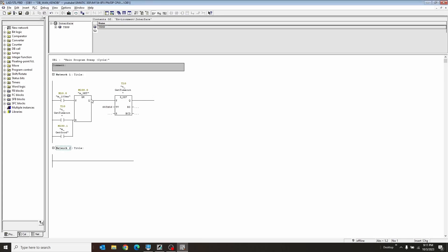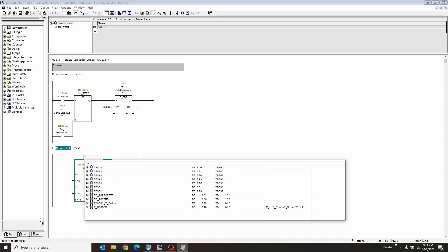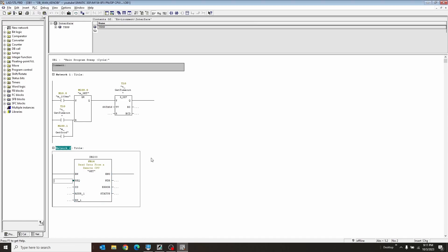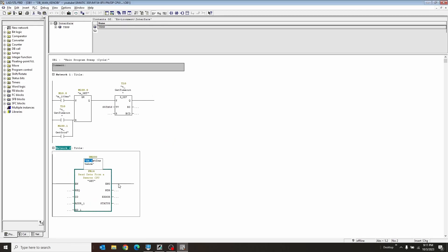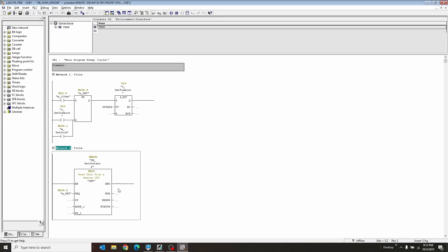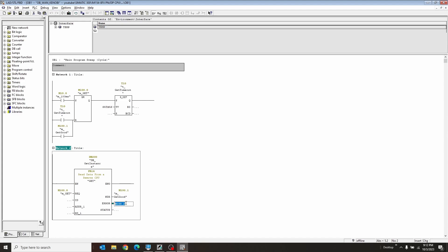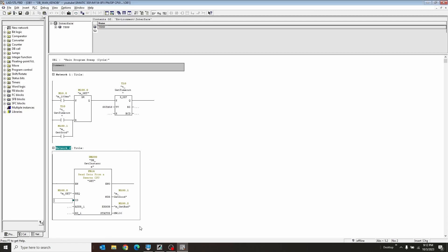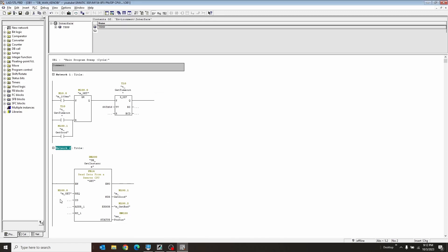So with that, I also want to create the actual get function. So here we can hit FB14. Here's our get function. I'm going to create a database. I'm going to call this database 200. Give him a name. So now what I want to put into here is the get command. That's going to be the REQ. The NDR is going to be the get good or new data ready is what that stands for. I'm also going to create an M100.2 here for an error if that were to happen. And then status.